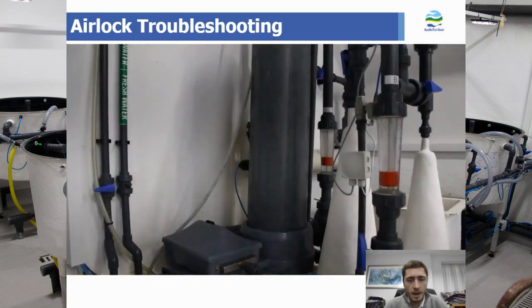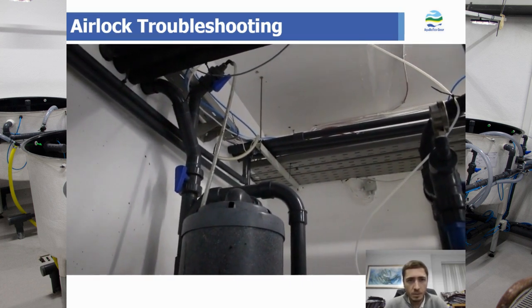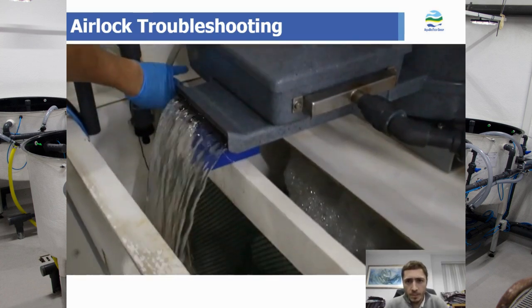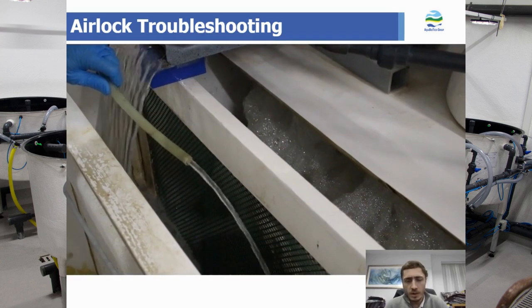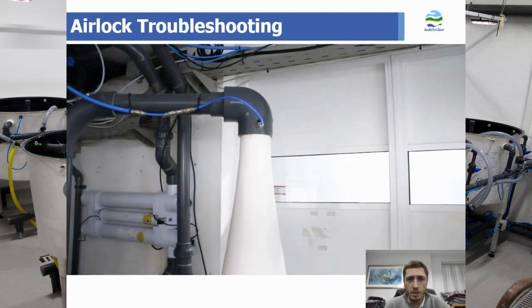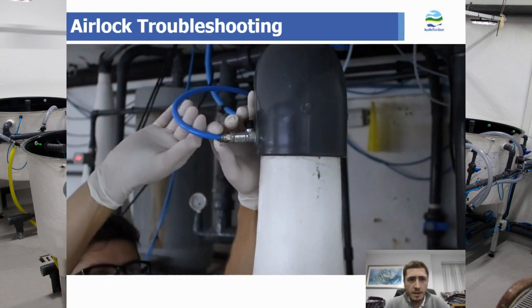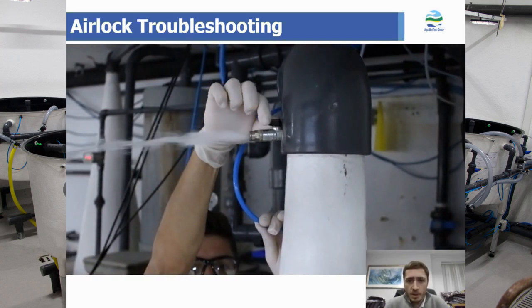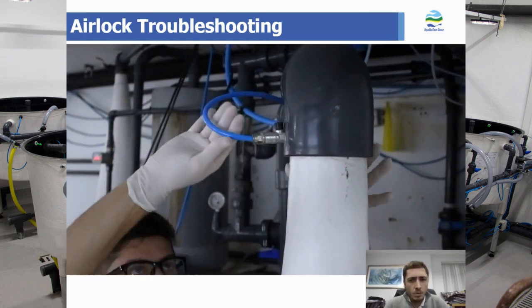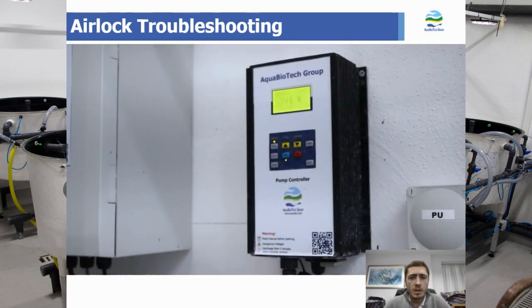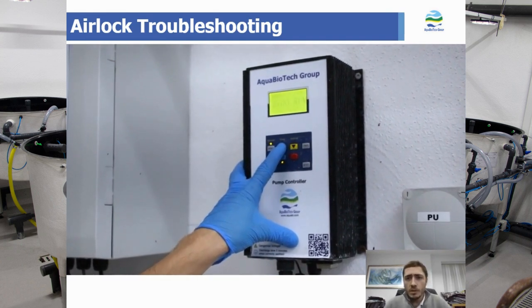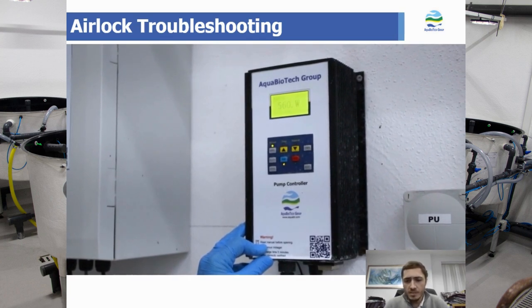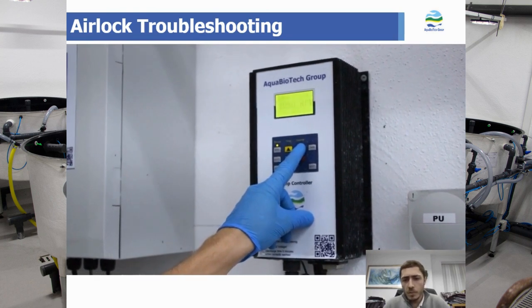So here we have a typical RAS. As mentioned, with most systems we have this air release valve at a high point in the pipework. In this case we have the valve partially open to ensure constant release of air. You can see it's connected with a hose to direct the water back to the clean sump — this is not always suitable as some systems are pressurized. As mentioned, air locks can also form at the point of a gas injection to a system such as at this cone. Here we can release the air through a dedicated release valve, or by removing the gas supply — ensuring that it's off first — and allowing the air to release until a constant flow is seen. Alternatively, if this doesn't work, we can use the pump control panel to momentarily ramp the pump up to try and force the air out. If successful, you might see bubbles coming out of the tank inlets or spray bars. However, some trials or species are sensitive to flow changes and this should be your last option — that depends on your situation.